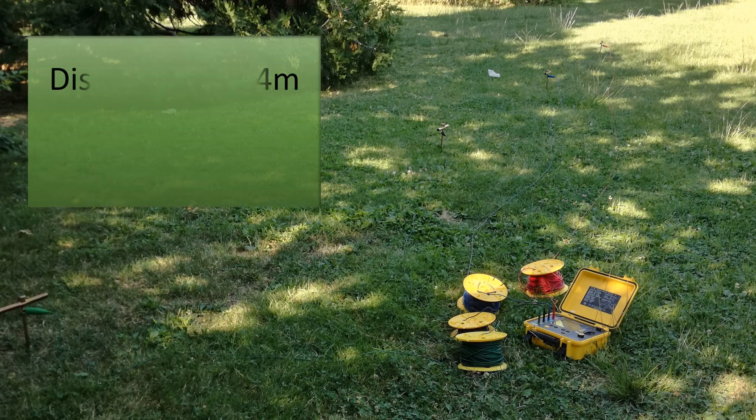Now, let's make an example of Wenner method. So, for our demonstration we will place the electrodes separated 4 meters and no more than 20 cm deep. In this case, we first determine the distance A, and from it, the depth of the electrode.